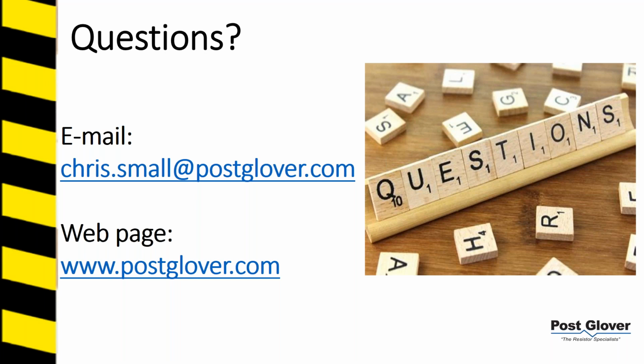A question from earlier in the presentation, and you kind of touched on it, but I think it's a good summary type question. Is it correct to assume that for medium voltage HRG system, we use it to reduce the fault current and then trip, but not necessarily for continuous operation? It depends on what your goals are, and once again, no. So when I keep saying it's a consensus for 5 kV and below, that means for continuous operation. So doesn't mean you can do it. You need to make sure that you can operate. There's a lot of people that prefer to operate their medium voltage high resistance grounds with a stipulation of tripping after 1 hour. There's other people that do it continuously.